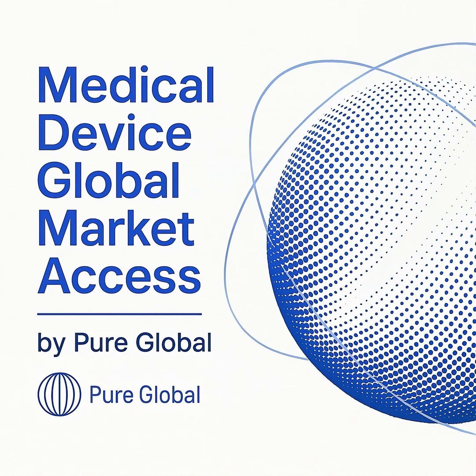Securing a positive NCD or LCD hinges on the evidence you provide. CMS evaluates evidence for what are known as analytic validity, clinical validity, and clinical utility. Analytic validity shows the test can accurately and reliably detect the specific analyte. Clinical validity demonstrates the test accurately correlates with a specific clinical condition. However, the ultimate requirement for CMS is clinical utility.